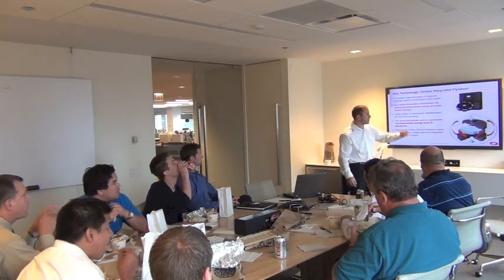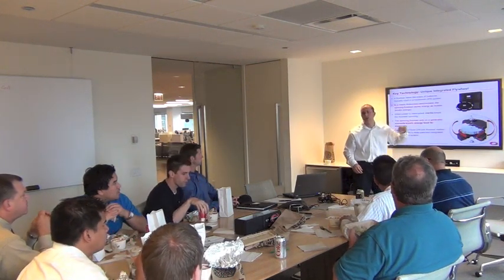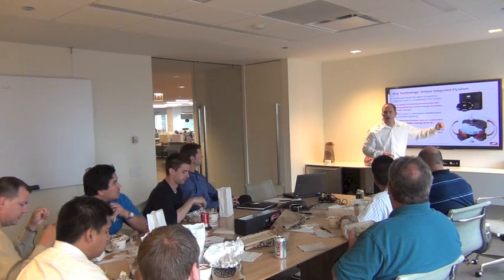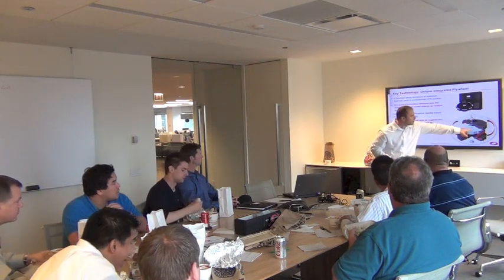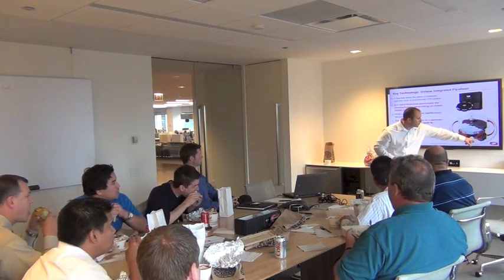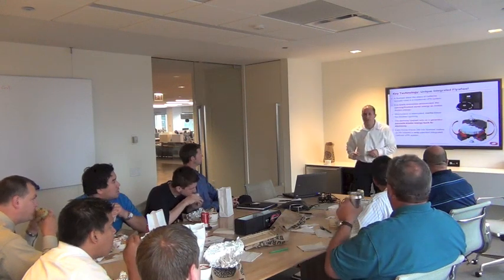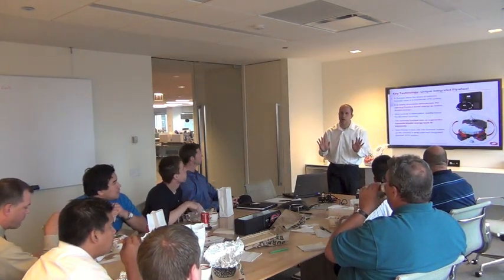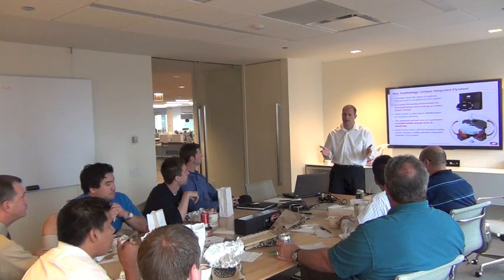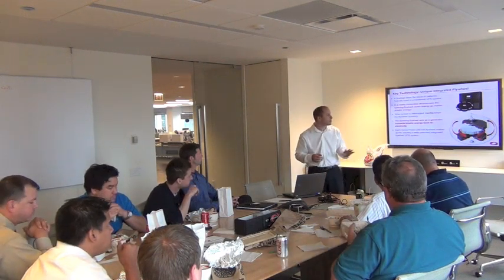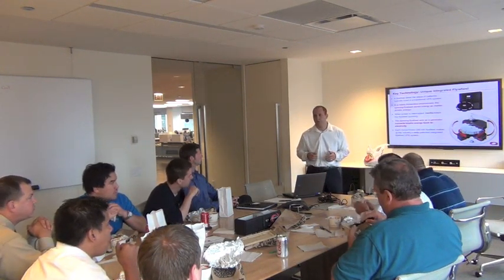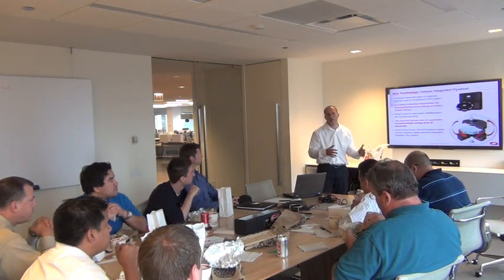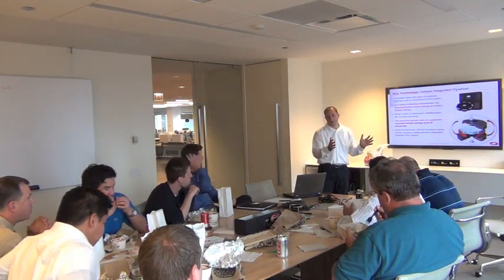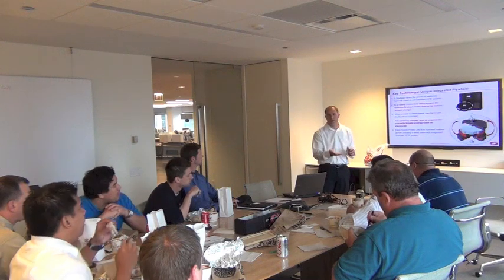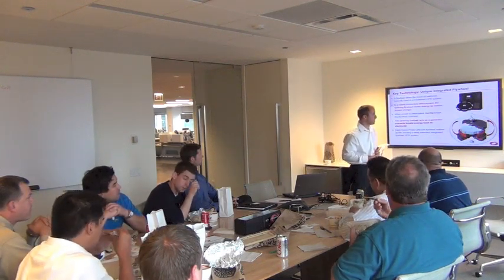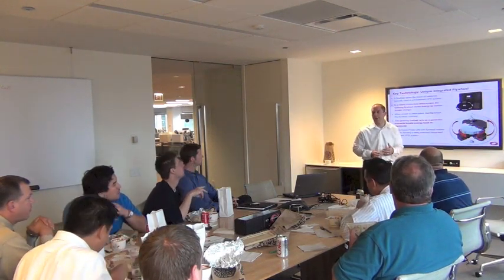So typically it's spinning at 7,700 RPMs. We're always pulling vacuum. It spins in about a 5 to 20 millitorr environment, so a very, very frictionless environment. We also inject a little bit more current in the lower field coils than we do the upper field coils, and what it does is it basically creates a magnetic unloading effect on the wheel. So even though the rotor weighs about 600 pounds, there's really only about 150 pounds on the bottom bearing. So again, it's spinning in about a 5 to 20 millitorr environment. We're magnetically unloading the majority of the weight of the rotor, so you only see 150 pounds on the bottom bearing. And that's very important to us to really spin in a frictionless environment. That way, we minimize losses.